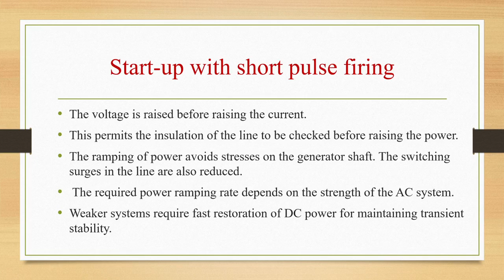Voltage is raised before raising the current, and this will permit the insulation of the line to be checked before raising the power. Ramping of power will avoid stresses on the generator shaft, and switching surges in the lines are also reduced. The required power ramping rate depends on the strength of the AC system. Weaker systems will require fast restoration of DC power for maintaining transient stability.